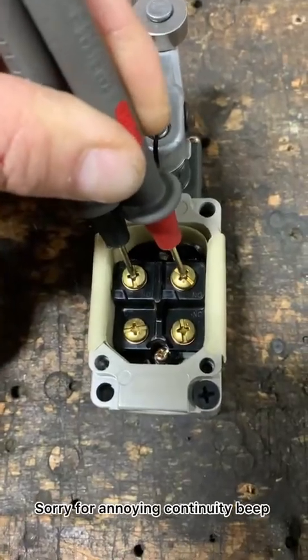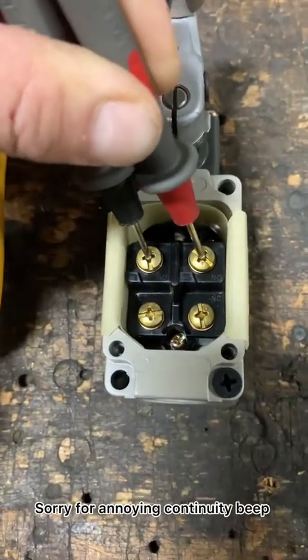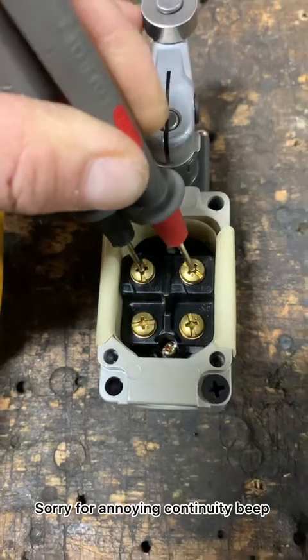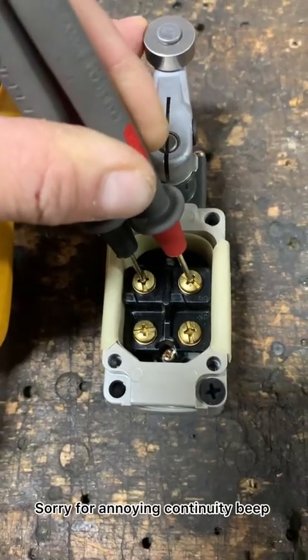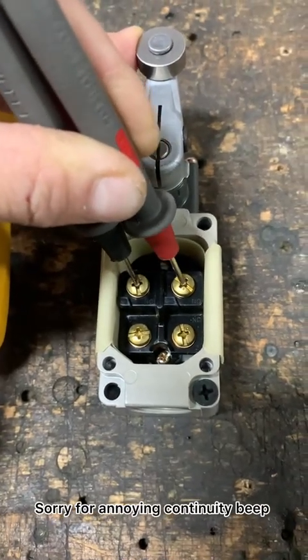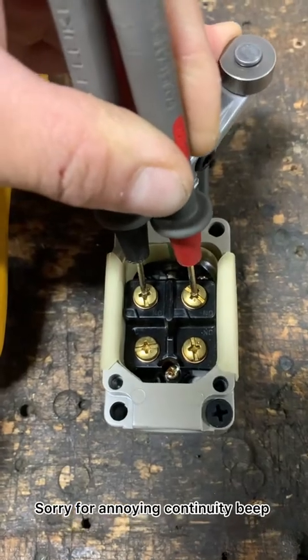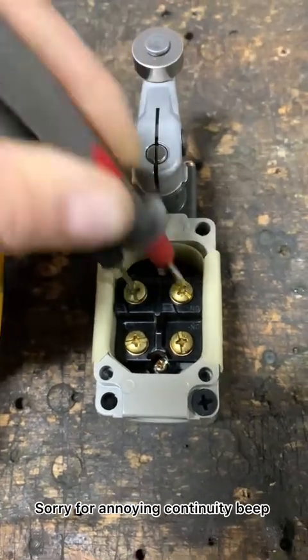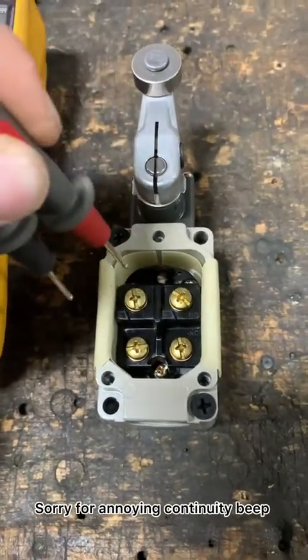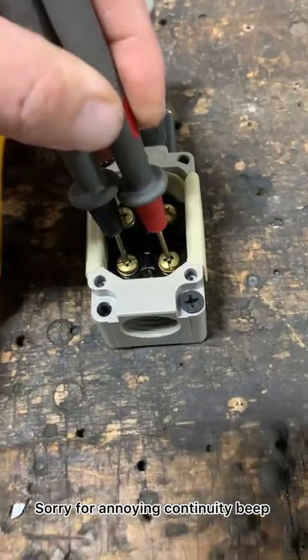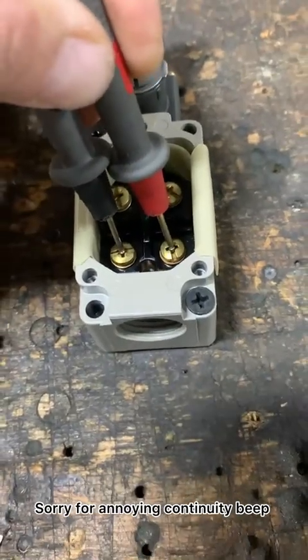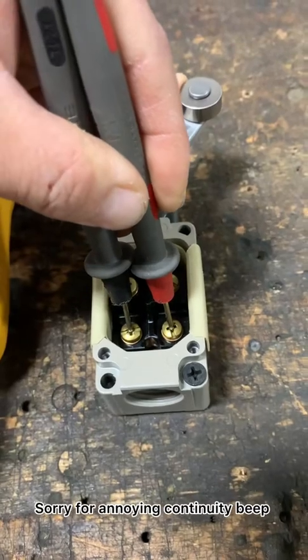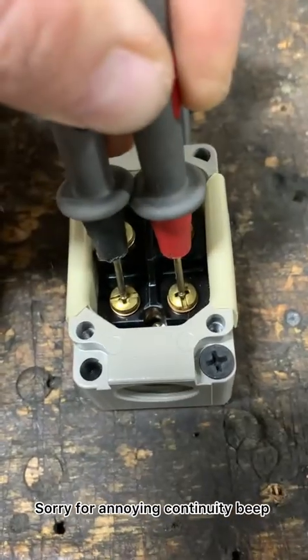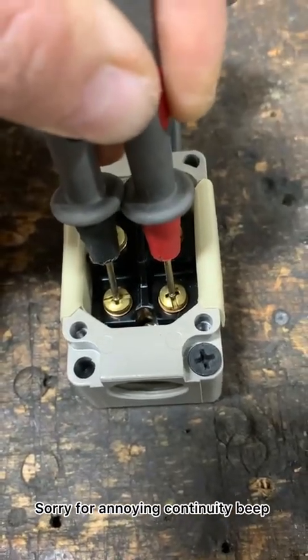And then to test to see if the contacts are working correctly, I have my meter leads on the normally opens. So right now there's no continuity, and as soon as I actuate the lever, the plunger switches, and now I have continuity. So I know these set of normally open contacts are good. And then down to my normally closed set of contacts, as soon as I actuate this lever, it's going to break continuity, so I know that this bottom set of normally closed contacts are also working.